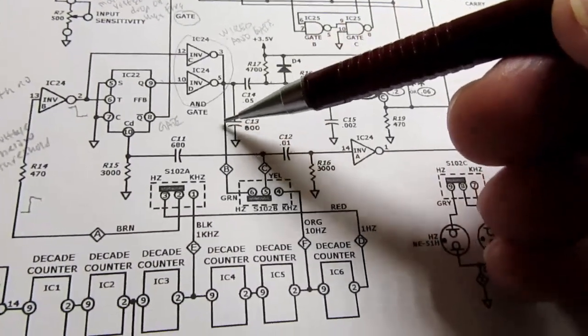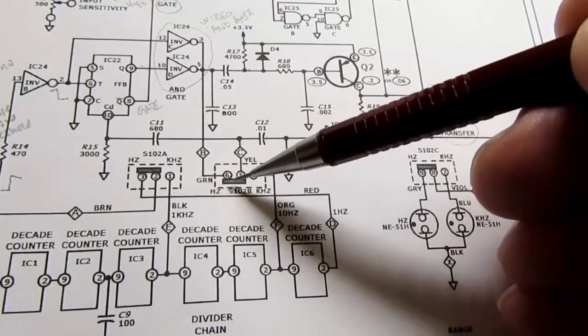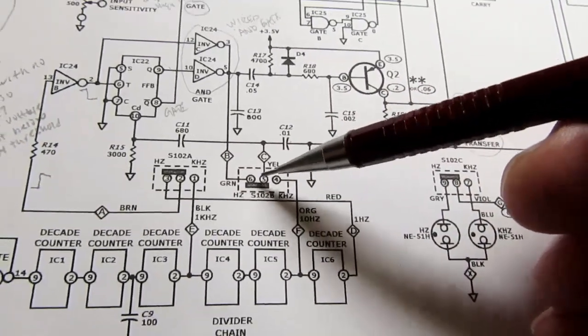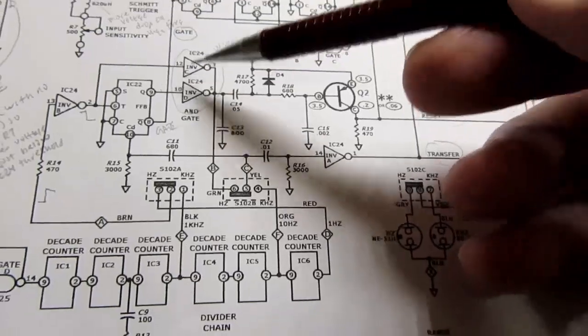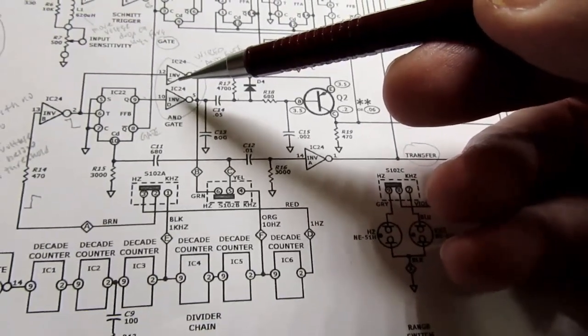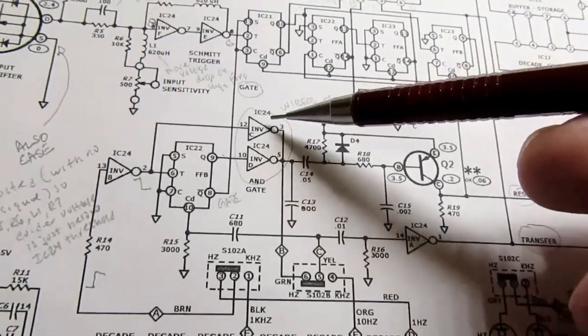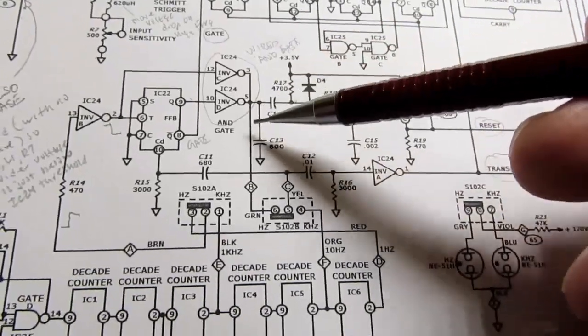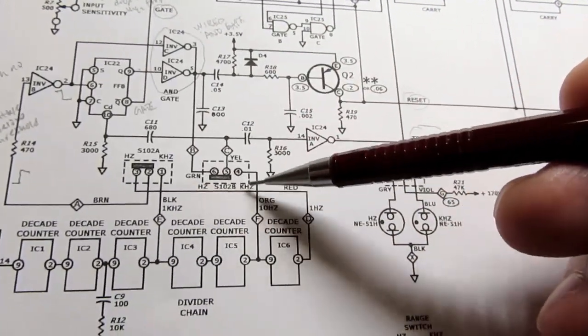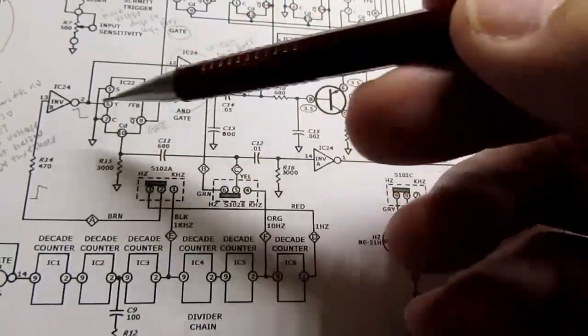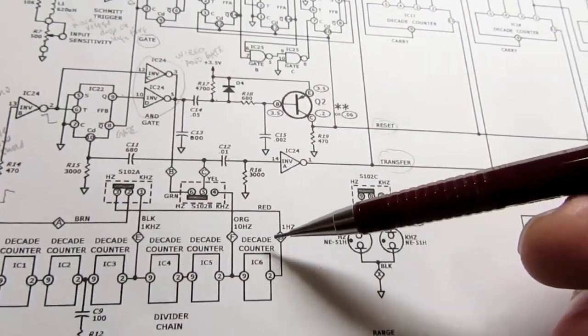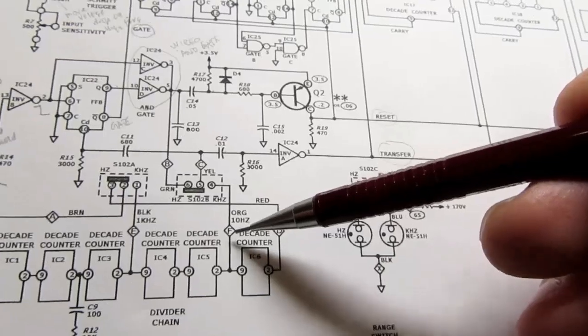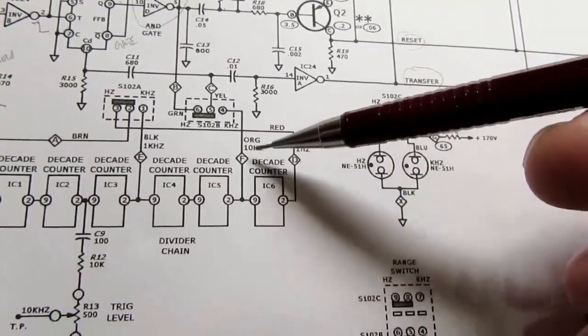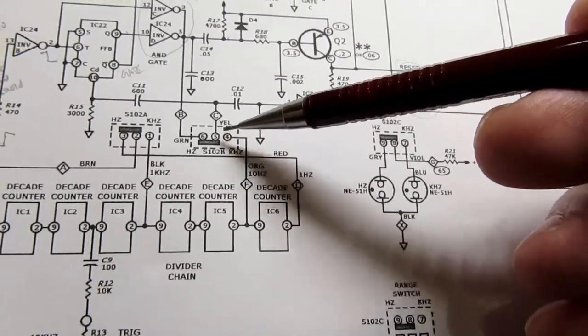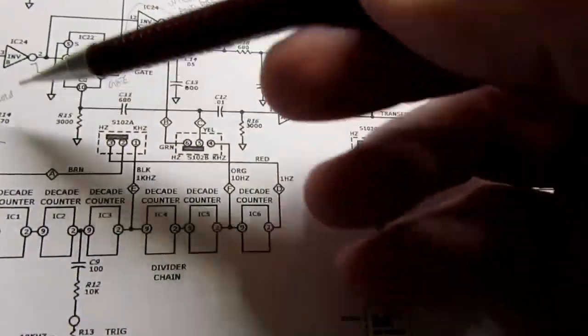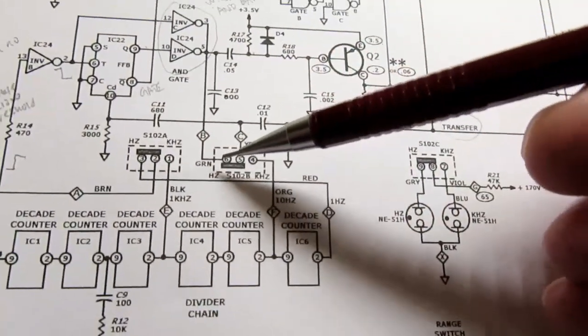This feeds down to here - another gang of the range switch. By the way, this is only necessary when you're in the slower range, the Hertz range. In the higher frequency range, this isn't so important. So we just use the 10 Hertz signal from this counter if you're in the kilohertz range, and you use this conditioned 1 Hertz signal if you're in the Hertz range.